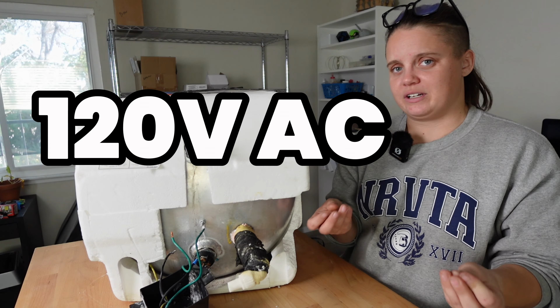If you do not, that means power is not making it to the water heater. This is the only way that this heater gets AC power. So if we are not seeing 120 volts at these wire nuts, we want to check: is our breaker on? Is our pedestal good? Are we getting AC power to other things, like is our microwave turning on? We need to start looking upstream because the AC problem is not with the water heater.